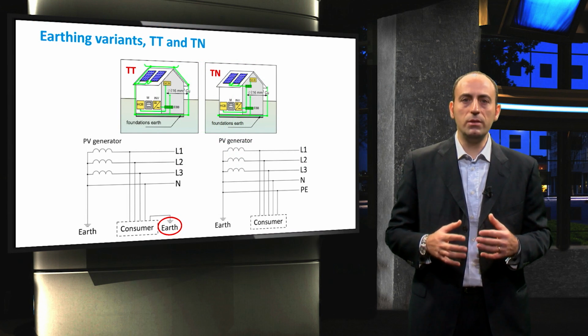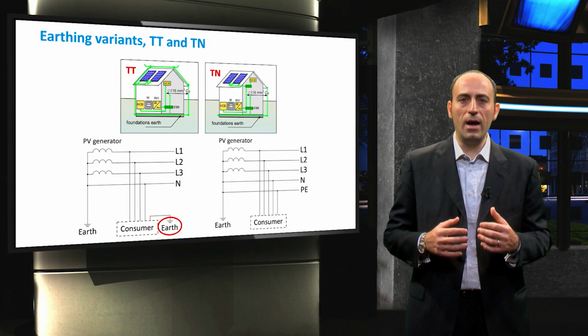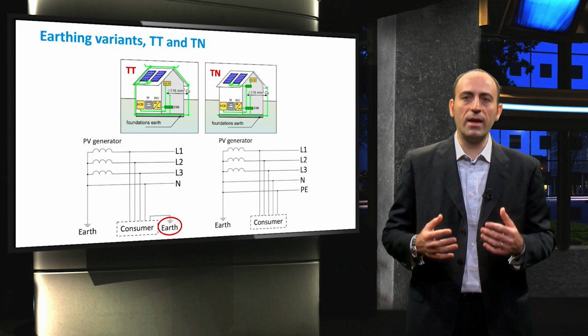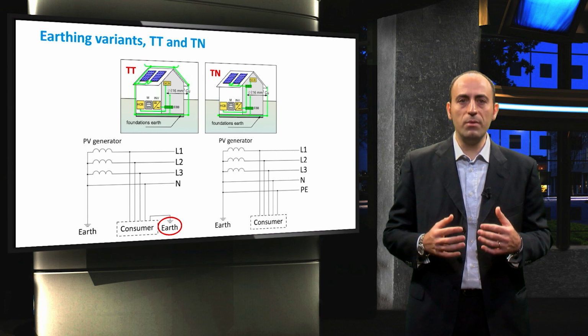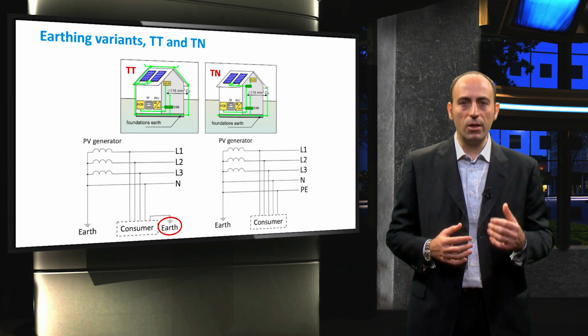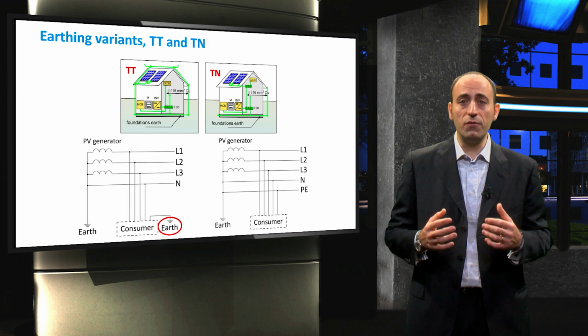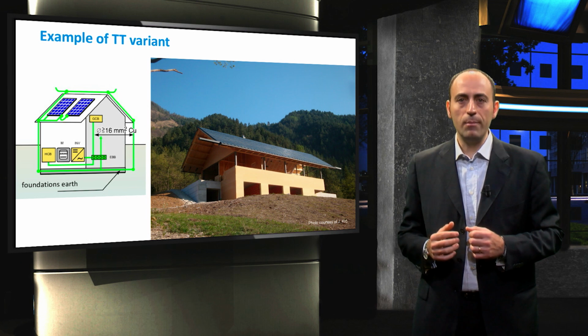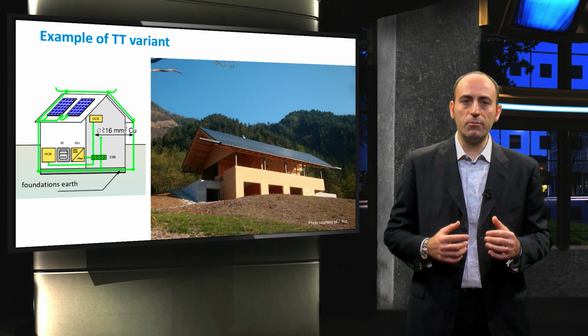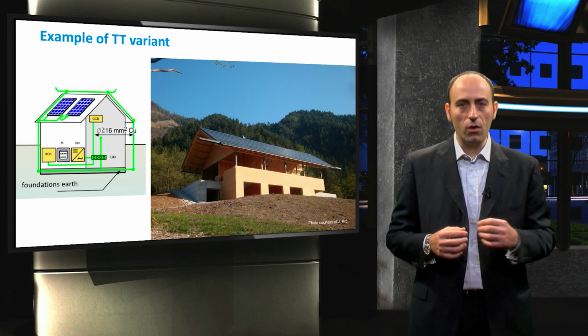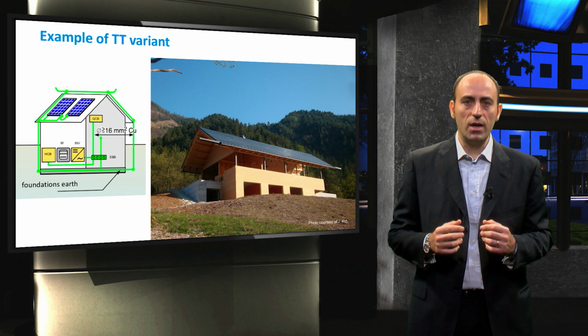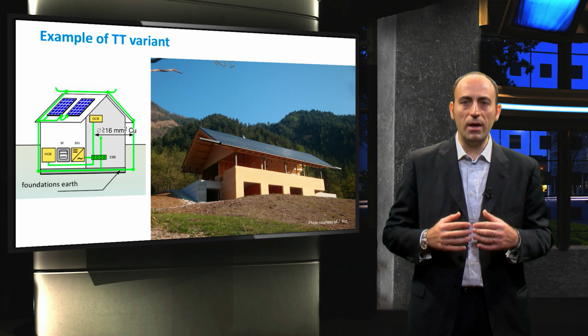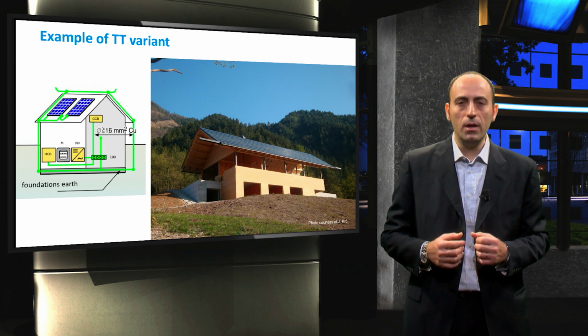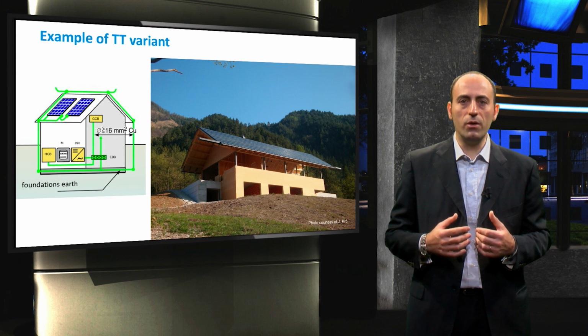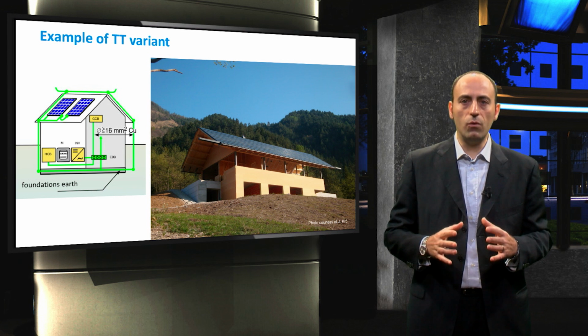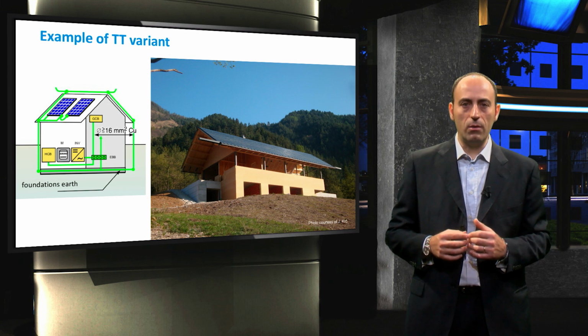The big advantage of the TT earthing system is that it is clear of high and low frequency noises that come from connected equipment, and thus TT has always been preferable for special applications like telecommunication sites that benefit from interference-free earthing. This is an example of a TT earthing system with the lightning protection made with a metallic structure along the roof. It is the simplest solution to design and install in systems supplied directly by the public low-voltage distribution network. It does not require continuous monitoring during operation, and it ensures that each installation fault results in an interruption in the supply of power.